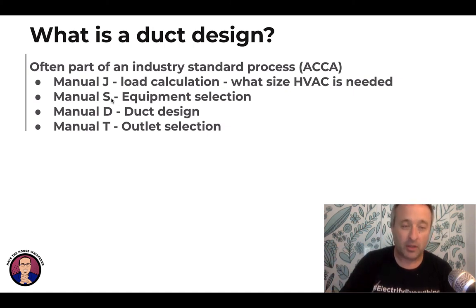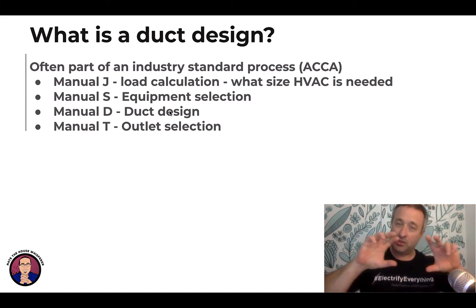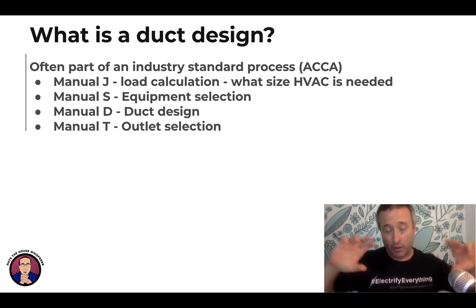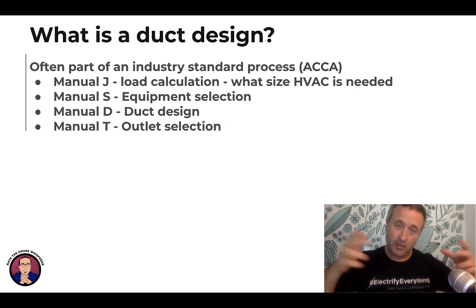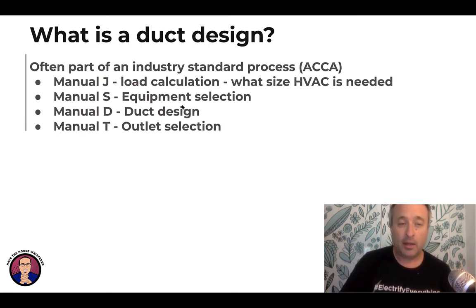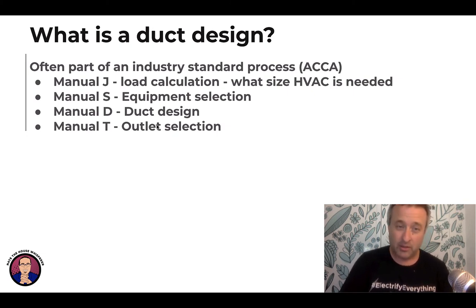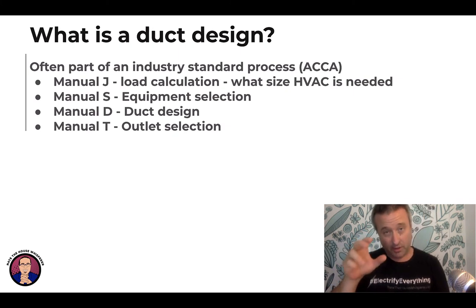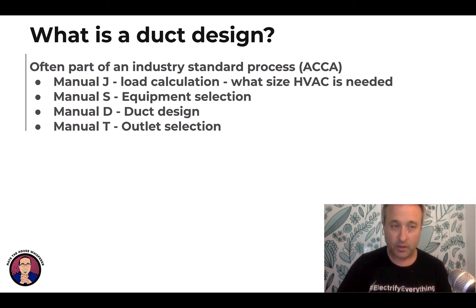Once you get Manual S done and select equipment, you do Manual D, which is the duct design. That determines what size trunks are, what size ducts need to come off to the different rooms, and how much airflow the room should get based on how many BTUs — how much heat or cool they need. Manual T is not done very often, but that is outlet selection: what kind of vents are you actually putting in the ceiling, walls, or floor. So that's Manual J, S, D, and T.